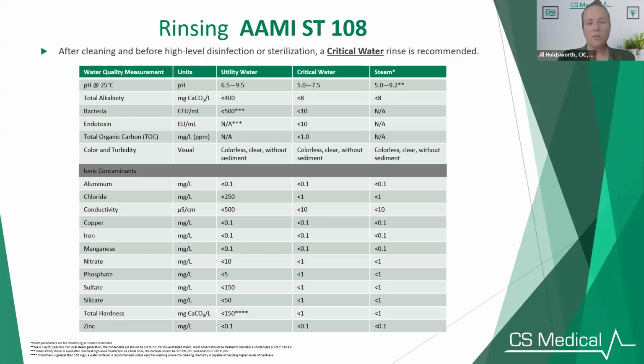So some of you may be doing your endocavity and or your TEE reprocessing in your SPD department. Some of you may already have an RO or an RODI system in your SPD department, which would qualify as critical water. Some of you may be doing some of this in cardiology and radiology and ultrasound, which may or may not, probably not, have critical water already going to that department. So if the IFUs are calling for critical water, then that is going to be something that's difficult to achieve. Next slide.